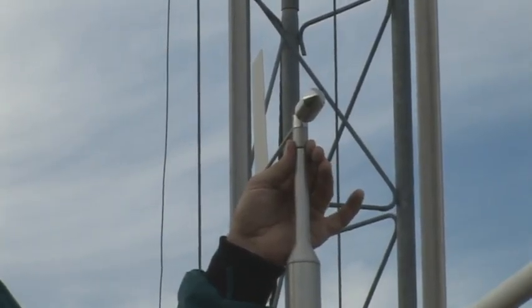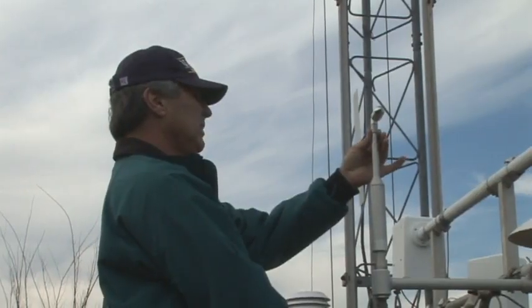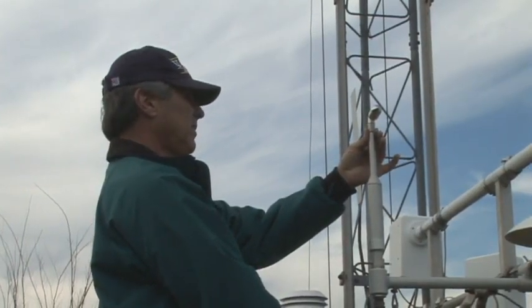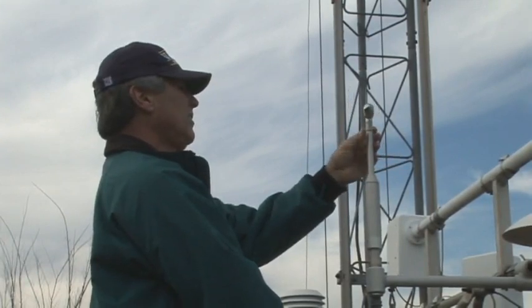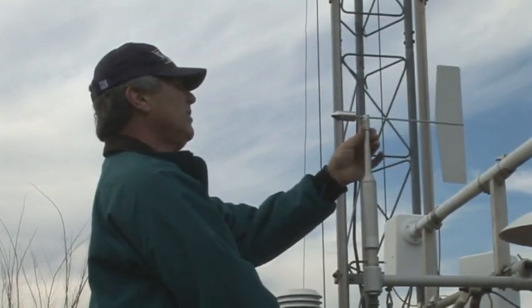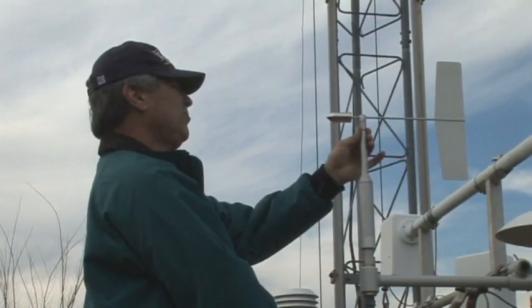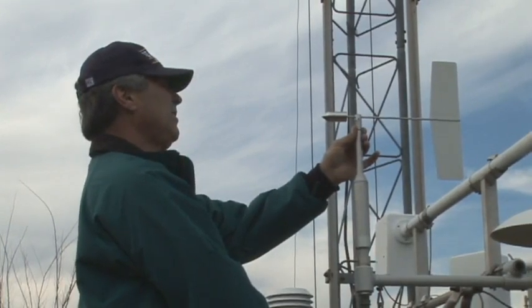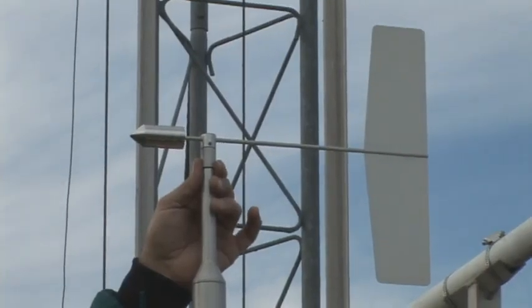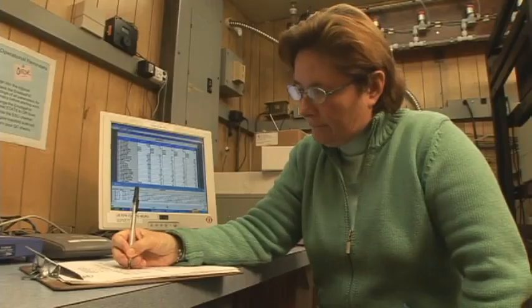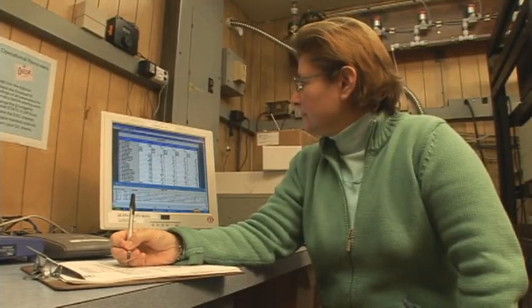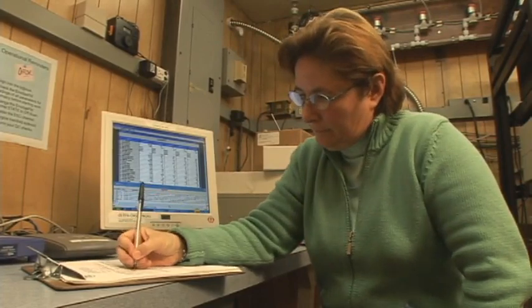The next point that will be performed is 180 degrees from the original point. Have the outside technician move the vane in a clockwise direction. With the wind direction vane in place, have the outside technician hold the vane so that the tail is in line with the instrument boom. Have the technician hold the vane as steady as possible. Once the vane is steady, have the inside technician record the response of the DAS.